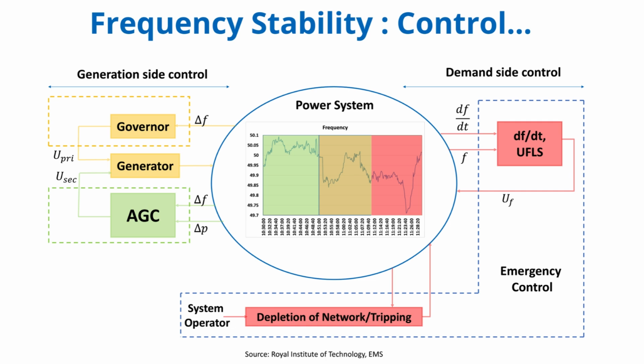Why? Because as we replace traditional generators, which have lots of physical inertia, with inverter-based resources, which often have little or none unless specifically controlled to provide it, the total system inertia decreases. Meaning the frequency change is faster for the same imbalance? Exactly. Higher df/dt.